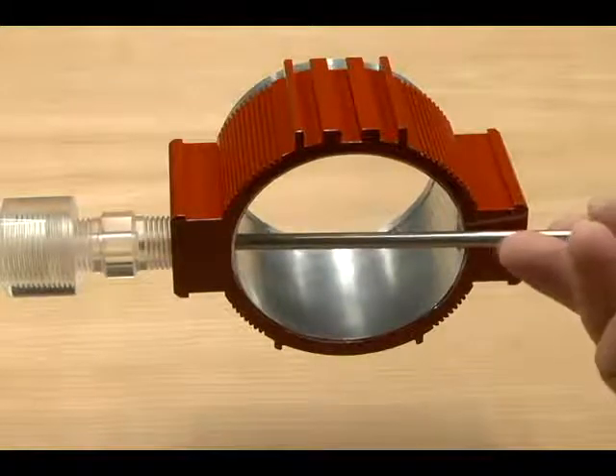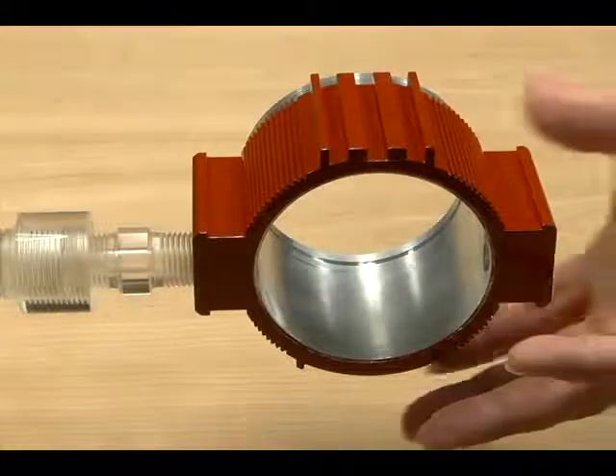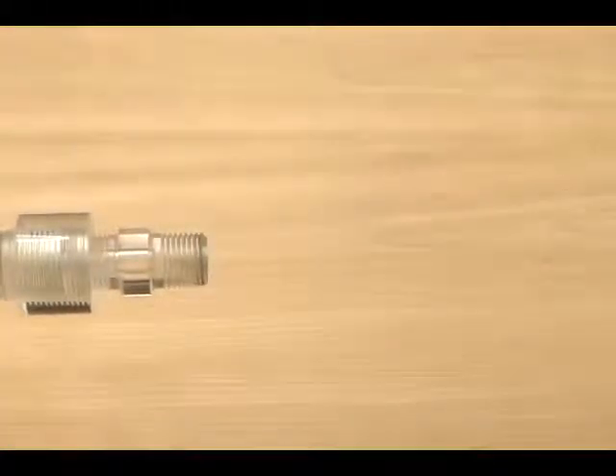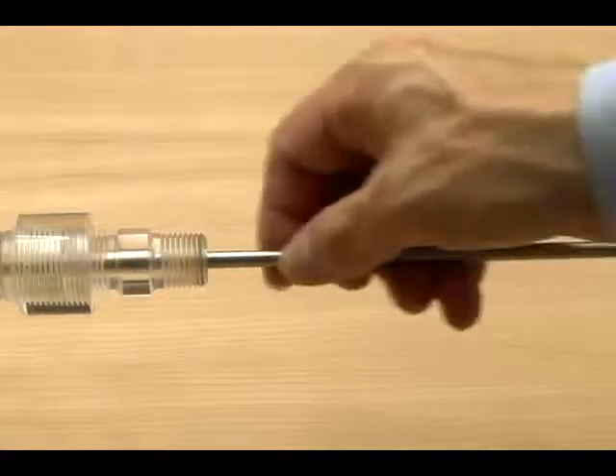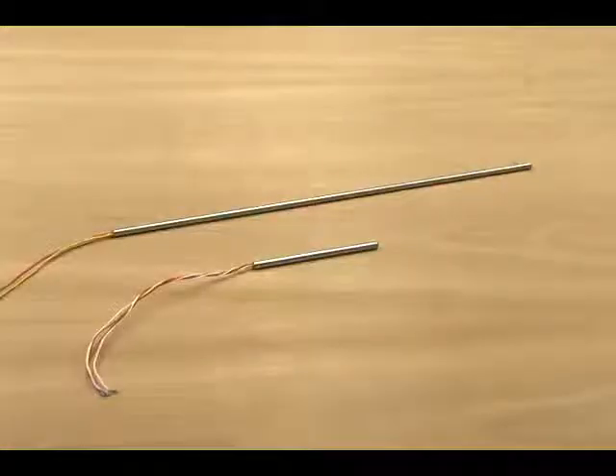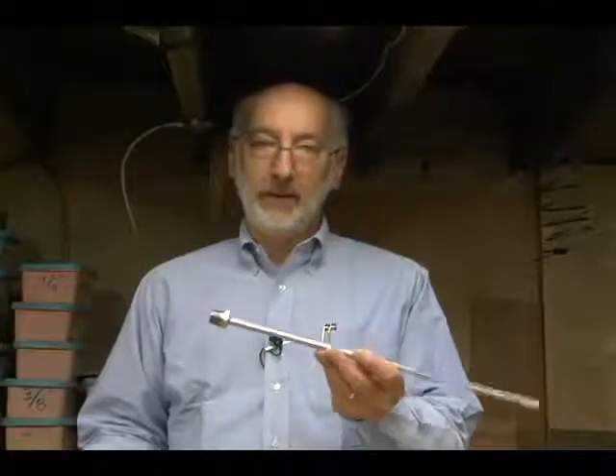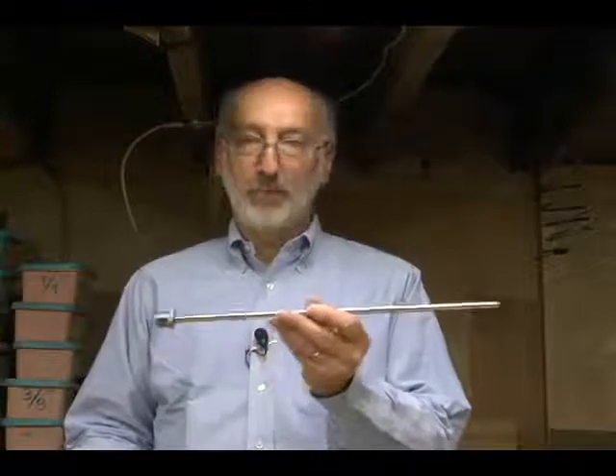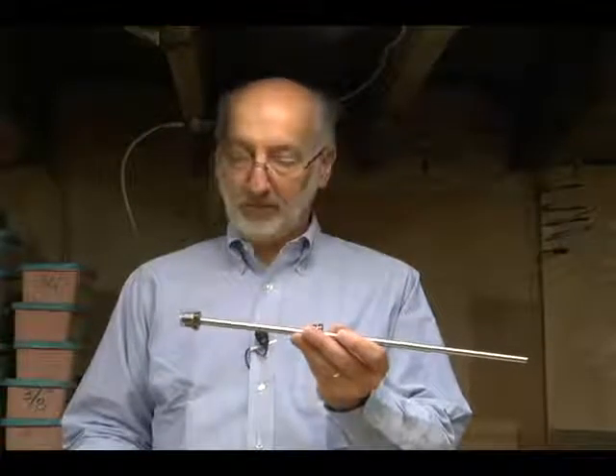In most cases, you will need to remove the transmitter housing, which makes the replacement process all the more complicated. Disconnecting and remounting wiring is always an invitation for problems. If the probe is not the same length as the thermowell, you have to stock a custom length probe. To make matters worse, the thermowell has to be perfectly straight and free from any internal debris.